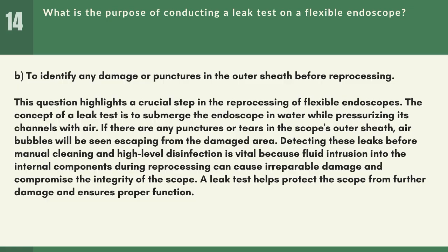Detecting these leaks before manual cleaning and high-level disinfection is vital because fluid intrusion into the internal components during reprocessing can cause irreparable damage and compromise the integrity of the scope. A leak test helps protect the scope from further damage and ensures proper function.